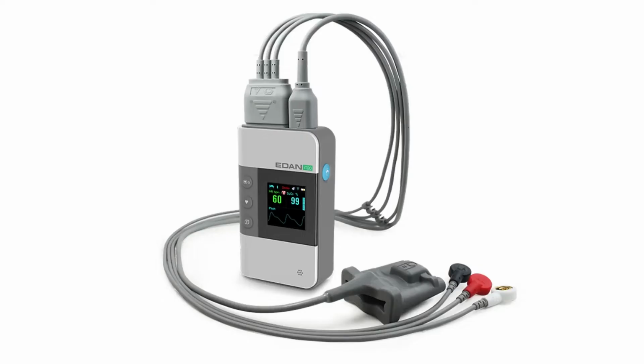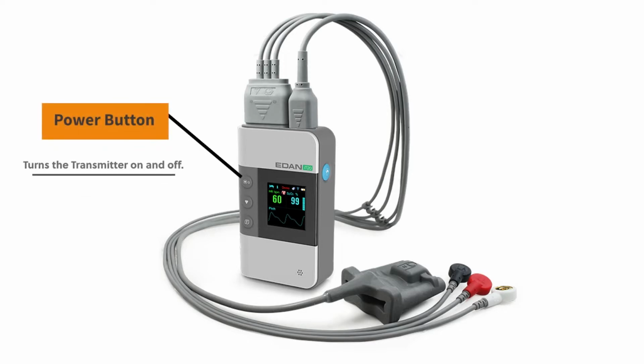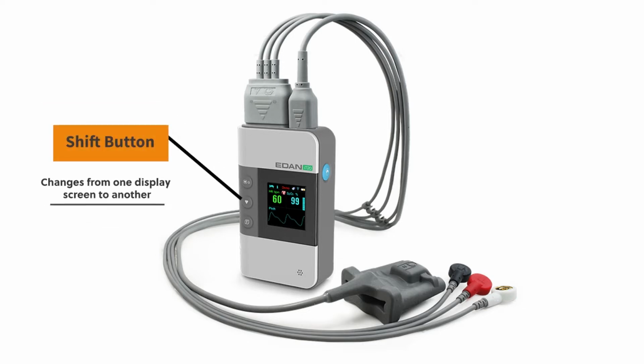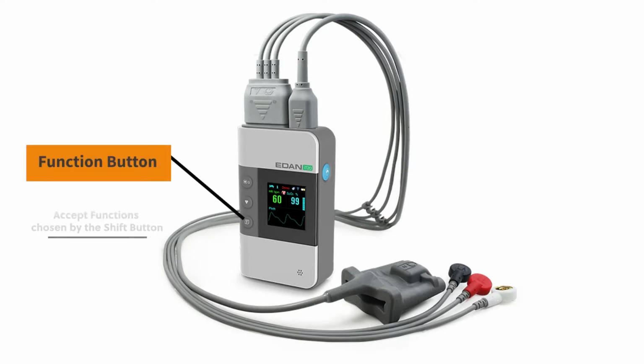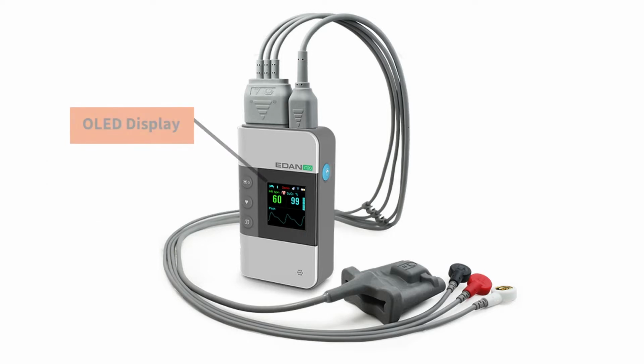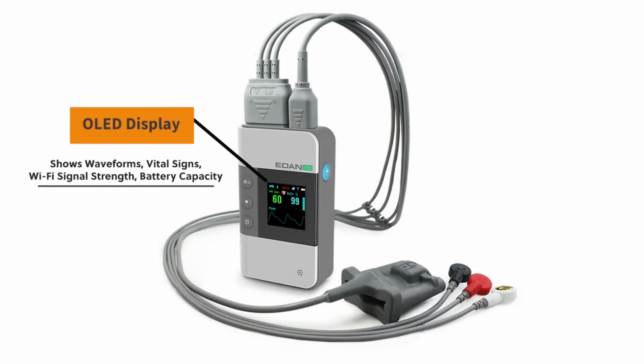Let's take an overall look at the layout of the IT20 transmitter. This top button is the power button, and is the one that turns the transmitter on or off. This middle button with the down arrow is the shift button, and is usually used to change from one display to another. The bottom button with the F on it is the function acceptance button, and is usually used to lock in a particular function that was chosen by the shift button. This is the transmitter's display and can show both waveform and vital signs numbers, as well as the signal strength and battery capacity of the device.